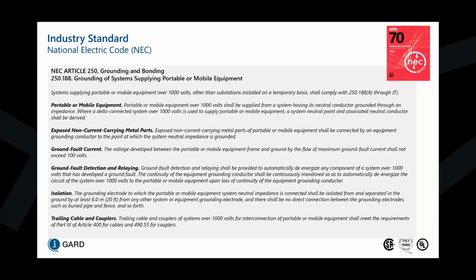And if your system is delta connected, you have to establish an artificial neutral using a zigzag transformer. Exposed non-current carrying metal parts of portable or mobile equipment shall be connected to an equipment grounding conductor to the point at which the system neutral impedance is grounded, and the voltage developed between the portable and mobile equipment frame and ground by the flow of maximum ground fault current shall not exceed 100 volts. In terms of ground fault detection and relaying, ground fault detection and relaying shall be provided to automatically de-energize any component of a system over 1,000 volts that has developed a ground fault, and the continuity of the equipment grounding conductor will be monitored to automatically de-energize the circuit of the system over 1,000 volts upon loss of continuity of the equipment ground conductor.